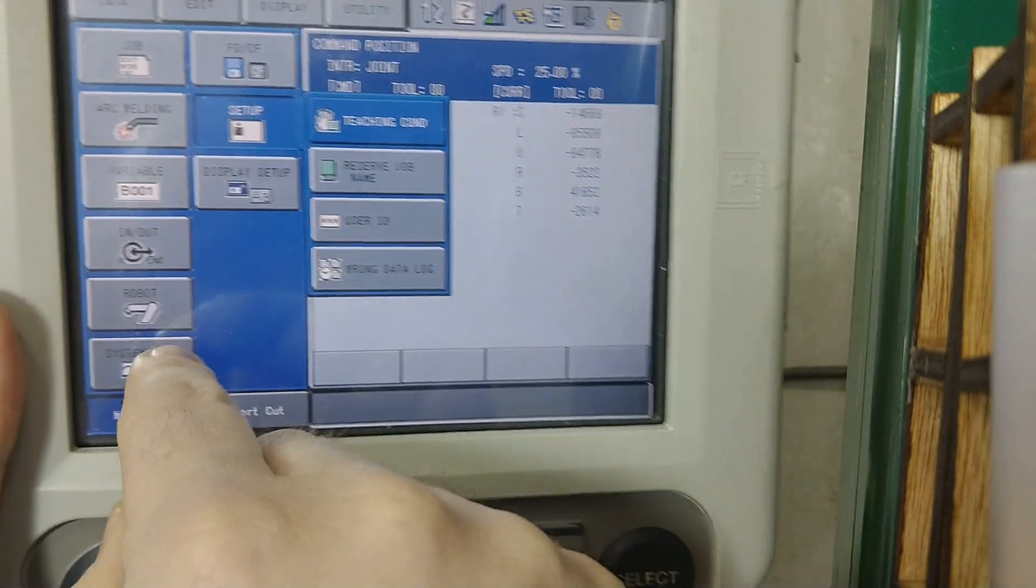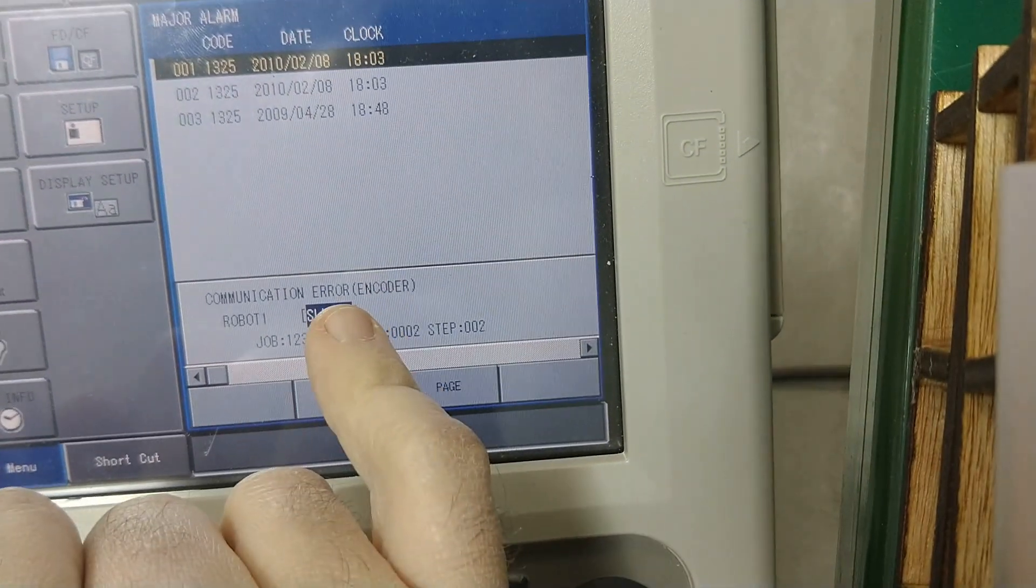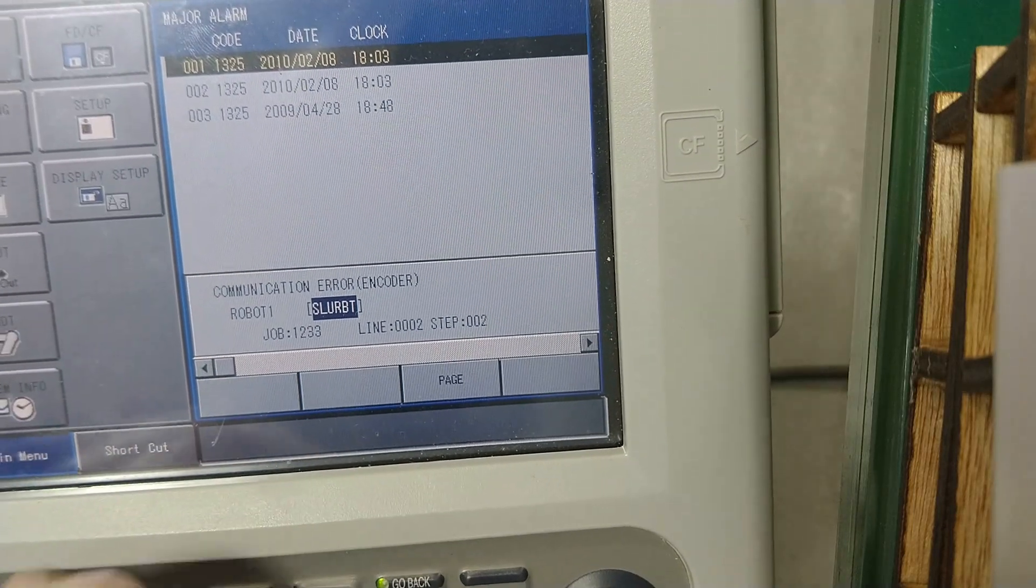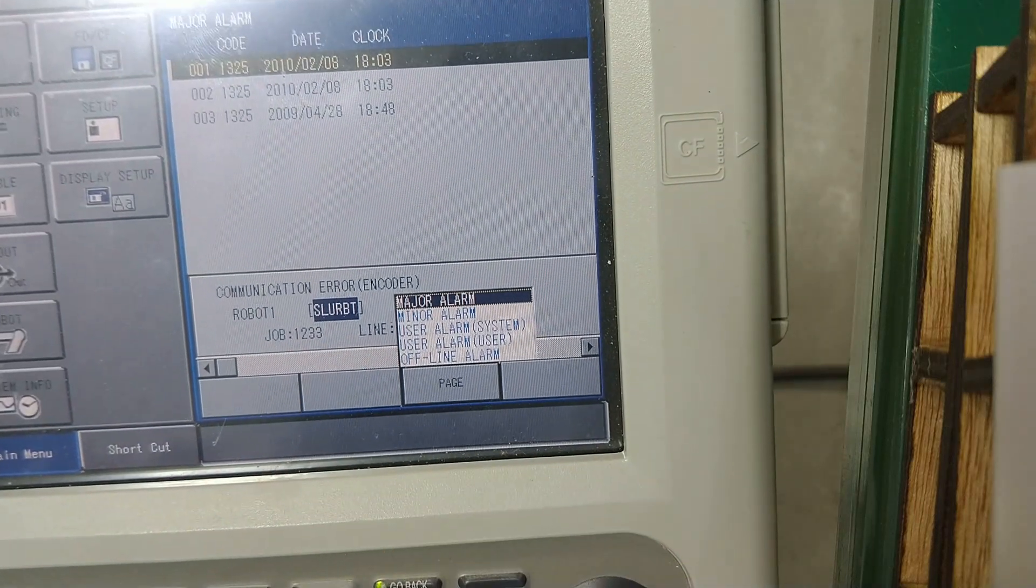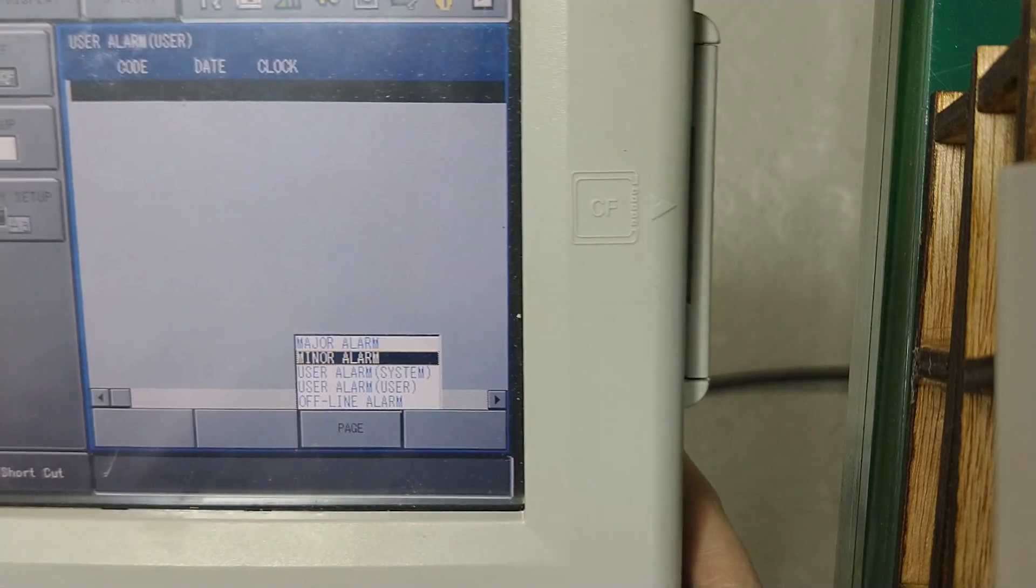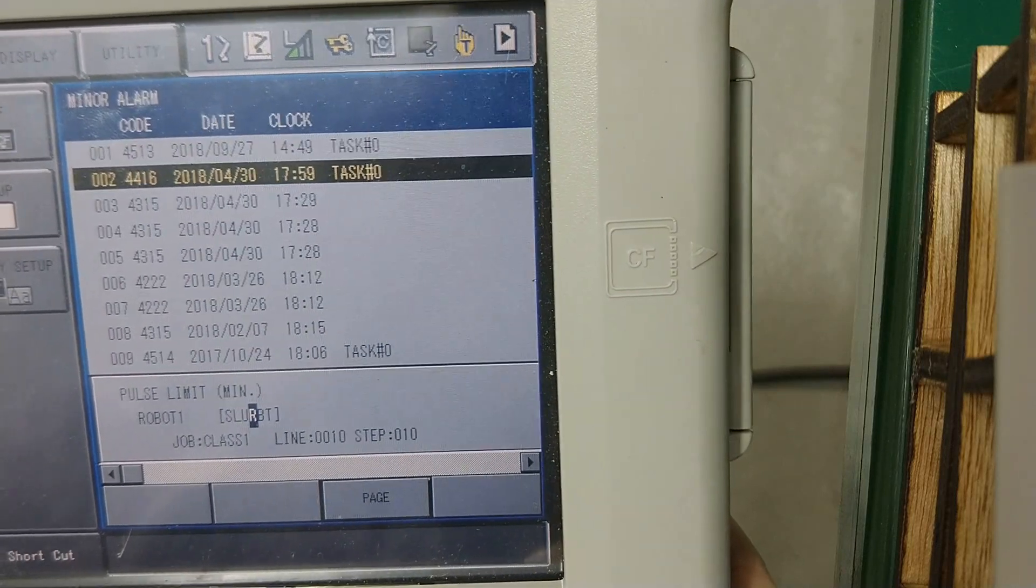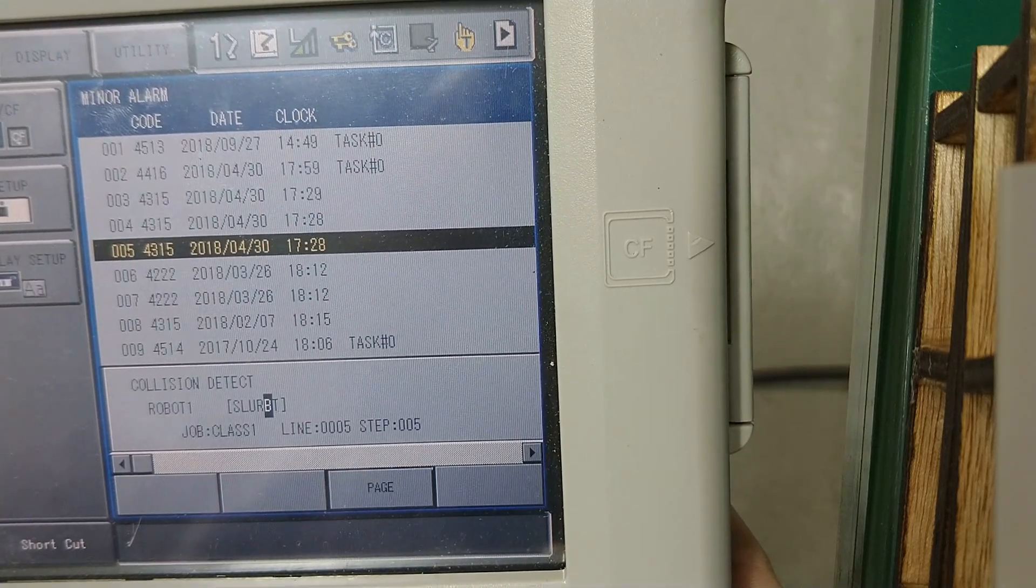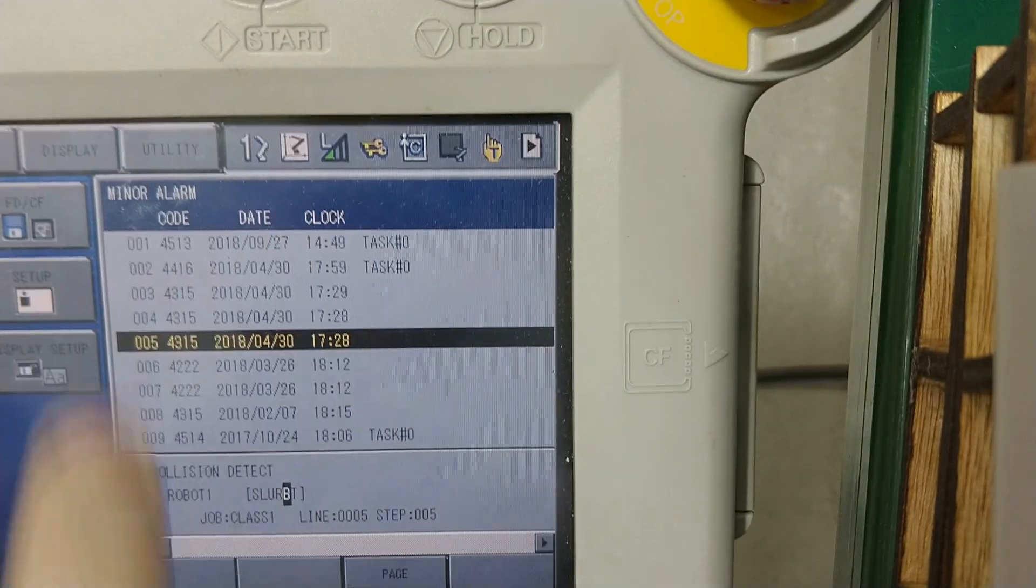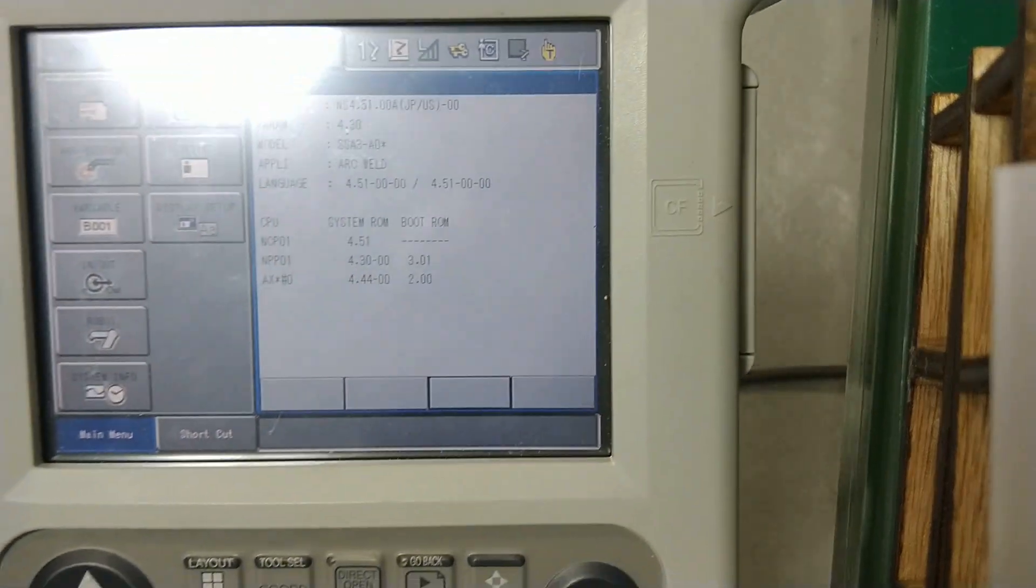Setup is where we can set up some of the other things. Setup user IDs, we're not going to worry about that too much. System info. This is where we can view alarm histories. We can see that in this case there was an encoder error way back in 2010. There's different alarms, major alarms, minor alarms. If I hit page, I can then use the arrow button to select down to user alarms. You can see different user alarms if there's any there. You can see the list of minor alarms, safety segments, that was fairly new. It'll give you the code and when and how and all that fun stuff. That's under system info, alarm history. You can click on your version. This will tell you what version you're running. If you ever call Motoman, they'll want to know all this.